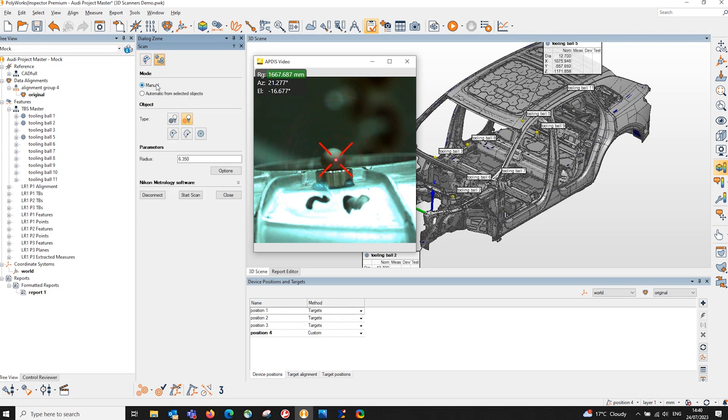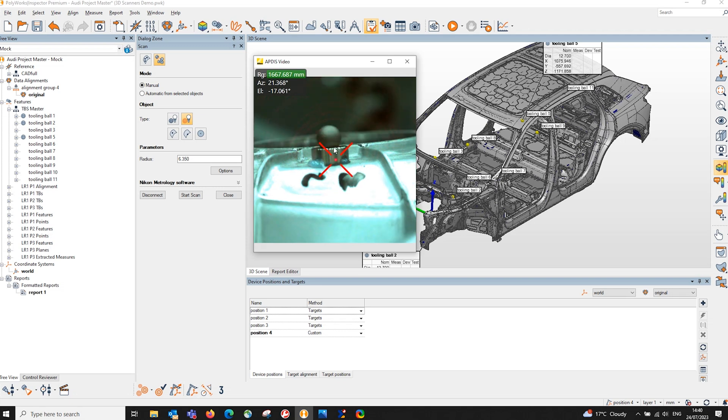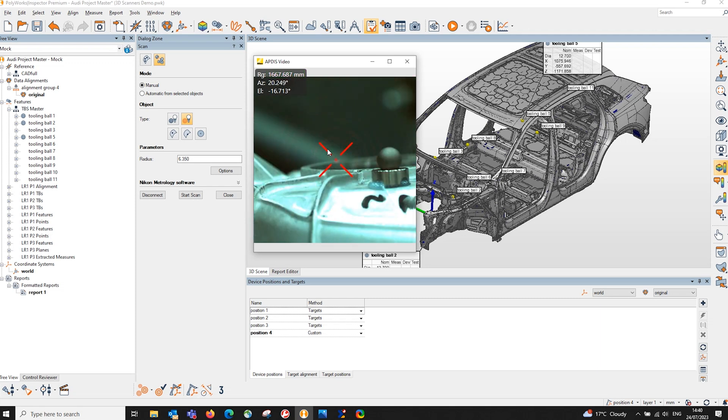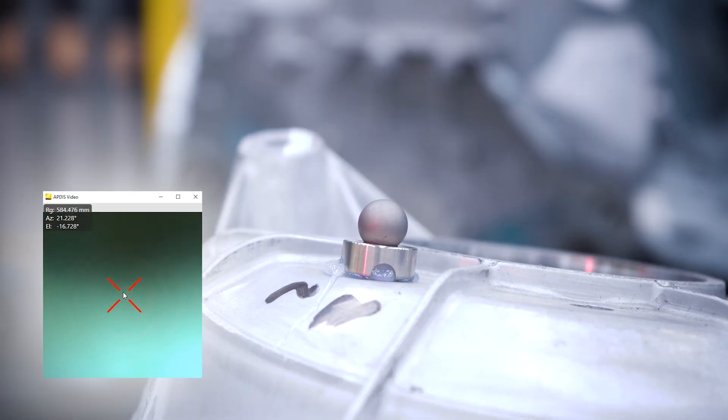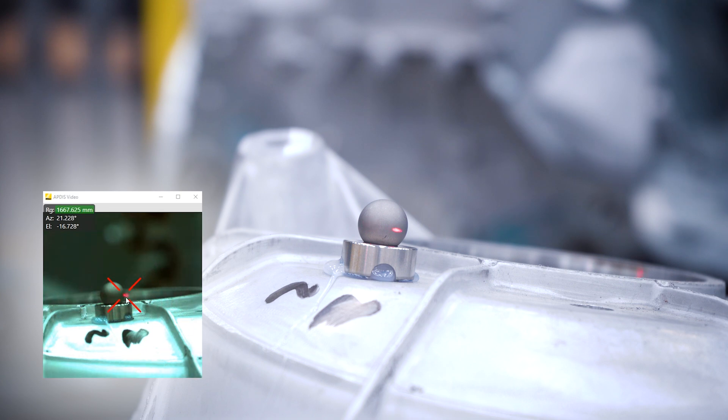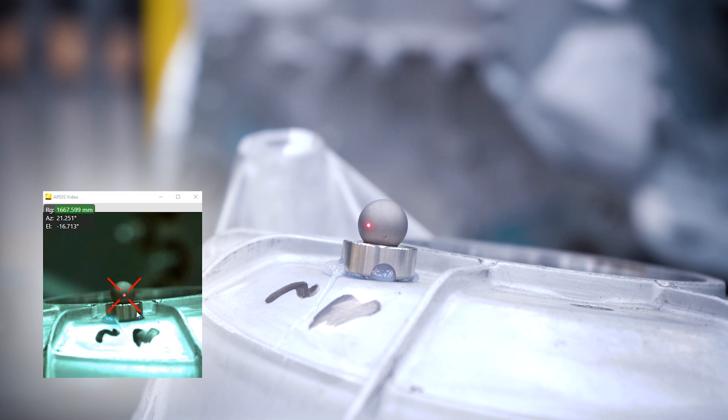We're interested in measuring objects. We can manually measure objects which we'll have to do initially before we do an alignment. I'll define some device position targets - you can see we're already aimed at one here. I can relocate or reposition the laser and camera by clicking on the screen itself, or I can hold shift and control on the keyboard and use my arrow keys to move around. F8 on the keyboard will focus the camera. When we're ready we say start scan and it will do a couple of passes over that sphere to create points to give us a device position target.